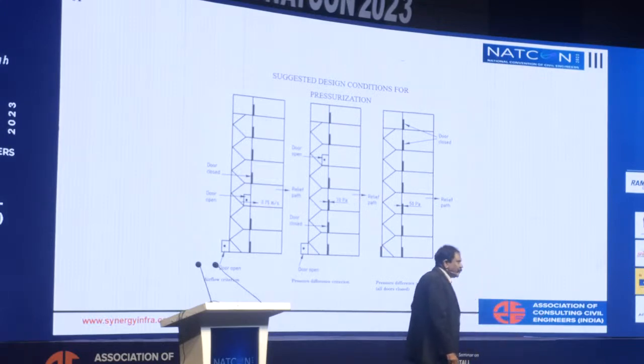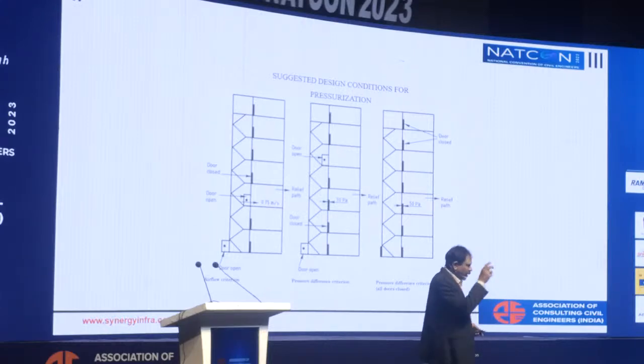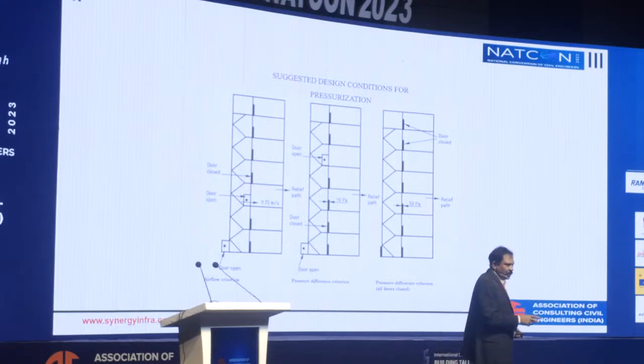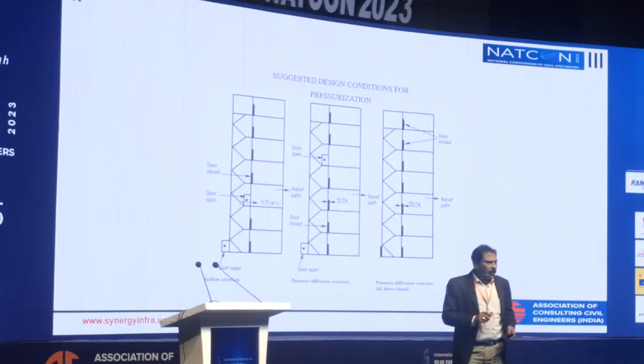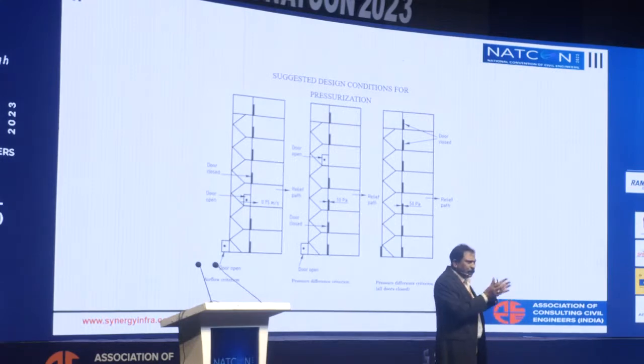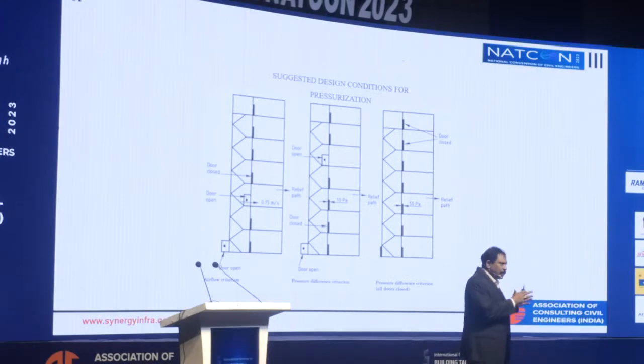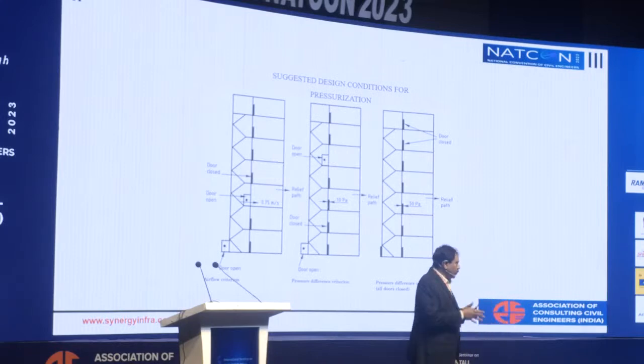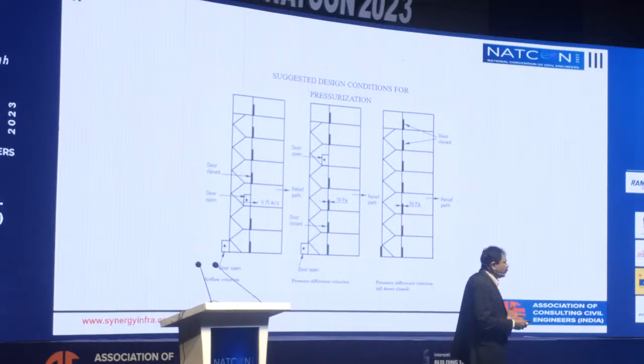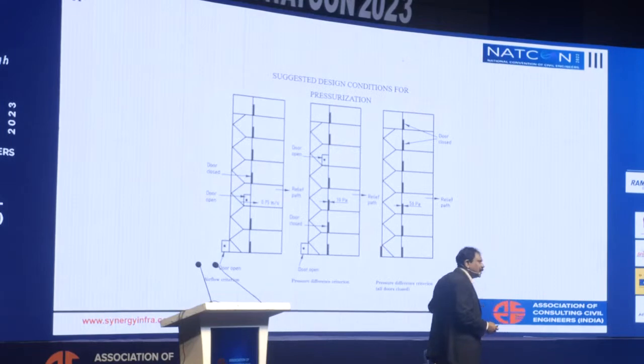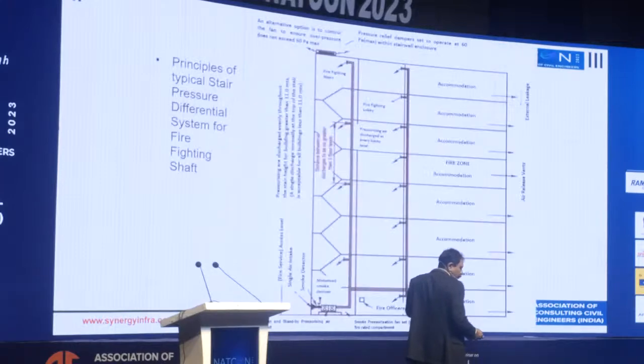Why I am telling you this is, if you design your firefighting and smoke management pressurization shaft for only 50 pascals when all the doors are closed, your shaft size is very small, because the air needed is only to take care of leakages around the doors. But the moment you open a door, the airflow required to maintain velocities of up to 0.75 meter per second across the door openings is quite huge. So the shaft sizes vary. Whenever we design these, a lot of discussion happens: why do you need such a big shaft, why can't it be smaller? Some people talk about only a small one. This is because there is no code, that is how it is done. But we need to look at logical relations and also consider how many doors are to be kept open in such a case.